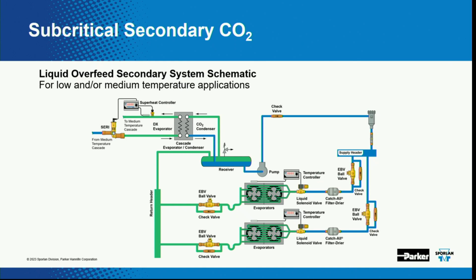And then check this out. It's just using a solenoid valve, because with an overfeed system, you've got more liquid going to that case than what you really need. Now there is a phase change in this coil, but because it's going to be saturated all the way through, I'm not going to superheat it at all. So all I need to do is put a set point on these and use a solenoid valve to just open and close. So I'm not metering refrigerant with an expansion device. I'm just opening and closing the solenoid valves.